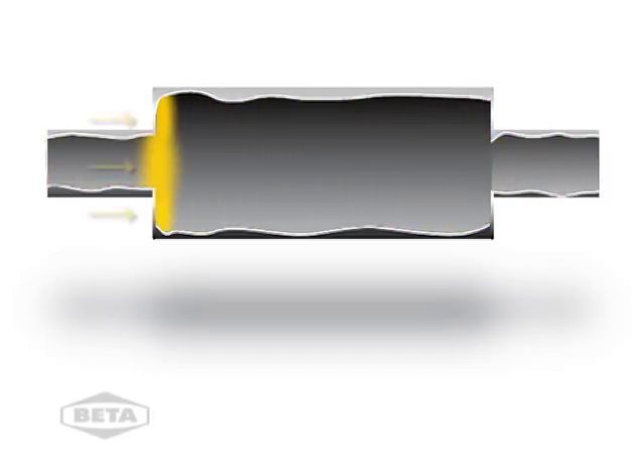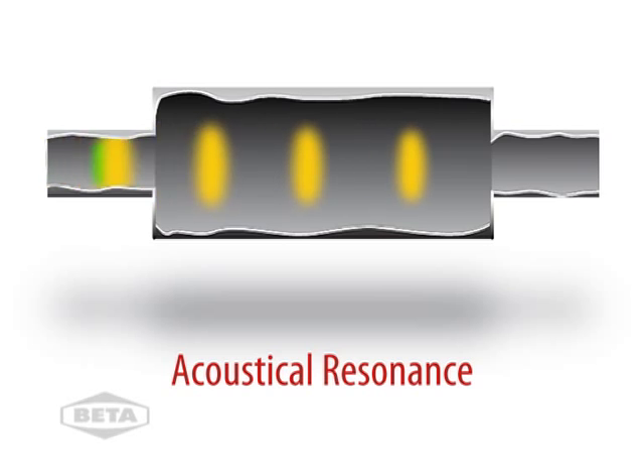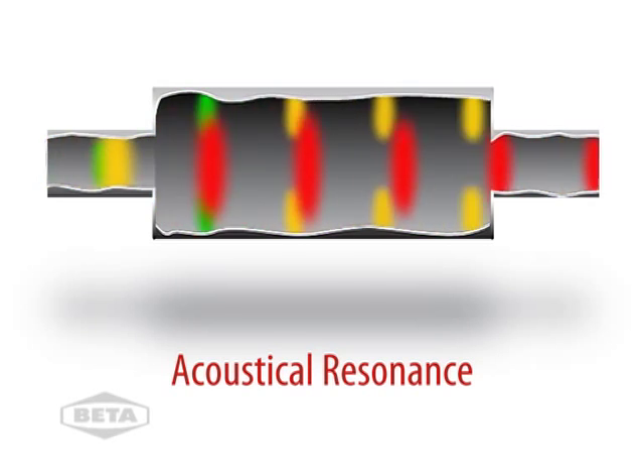Now the reflecting waves are in phase with the main wave, and the maximum has been reached. This is called acoustical resonance, because the reflections are in phase with the primary pulse. The pressure wave can be amplified significantly, even up to 50 times higher than the original wave.